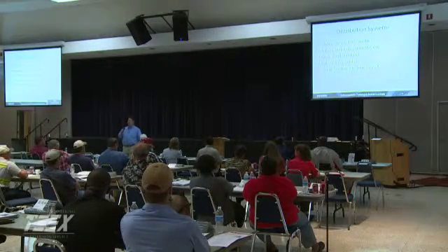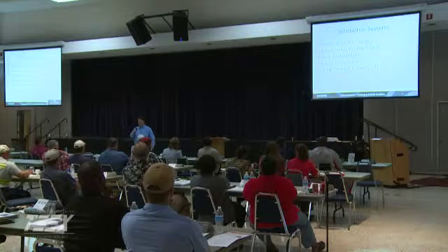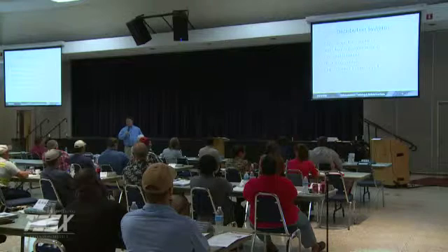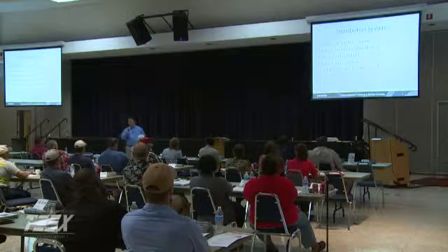Now remember, this 15 is under worst case scenario. You obviously don't want to run your system at 15 PSI regularly because you're going to start getting a lot of phone calls. People don't like it, especially if you've got a customer up on maybe a third floor of a building.